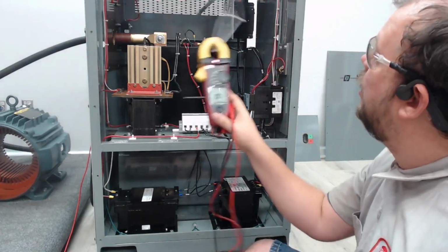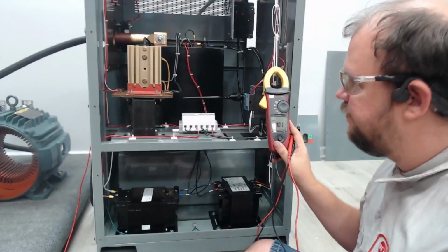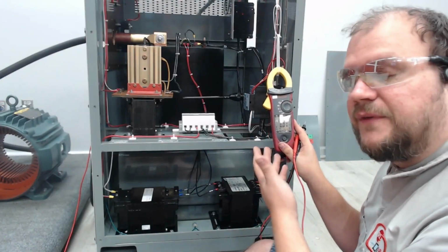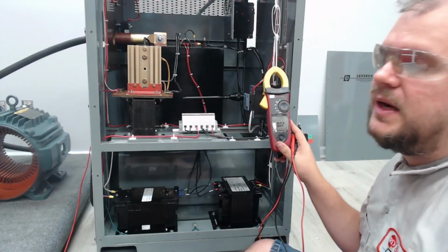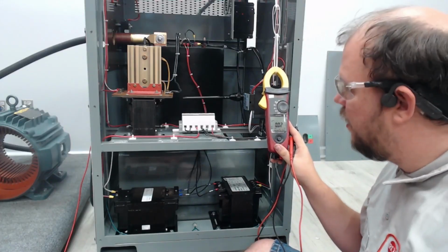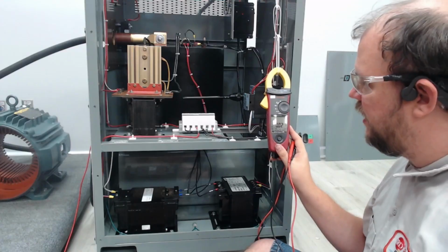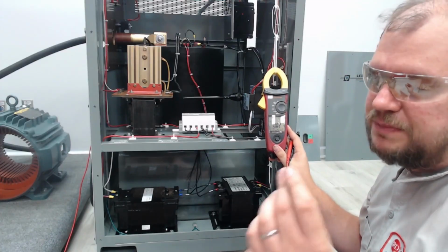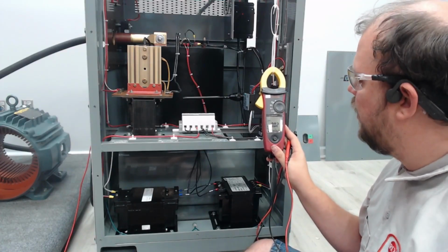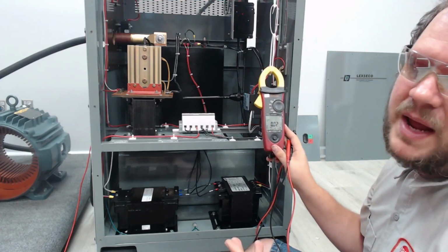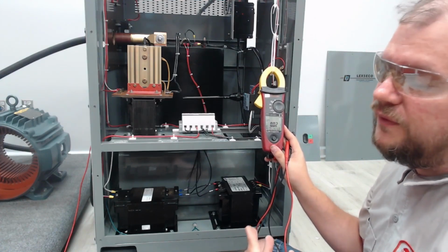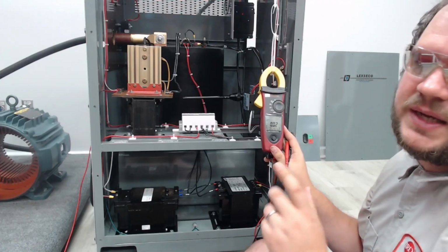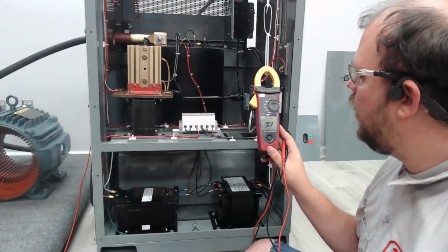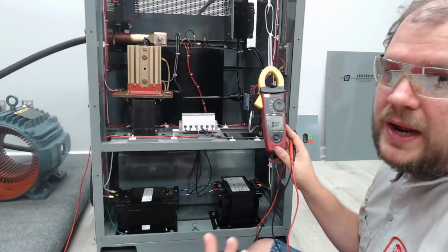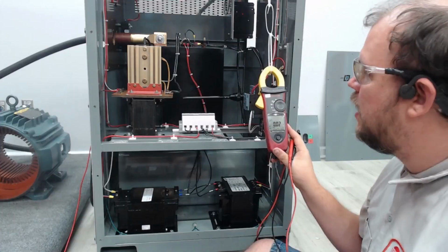For those who are dealing with fuse blowings, 1 and 2, you might need a pack of 20, I'm afraid. You might be going through a lot of these because you'll only be able to take these readings for a split second. And that's where using the min-max function of the meter can be really helpful. You just have 1 single second to get the min number to see if there's a voltage drop. And that's all you can do, and you'll just have to replace the fuse and go on.